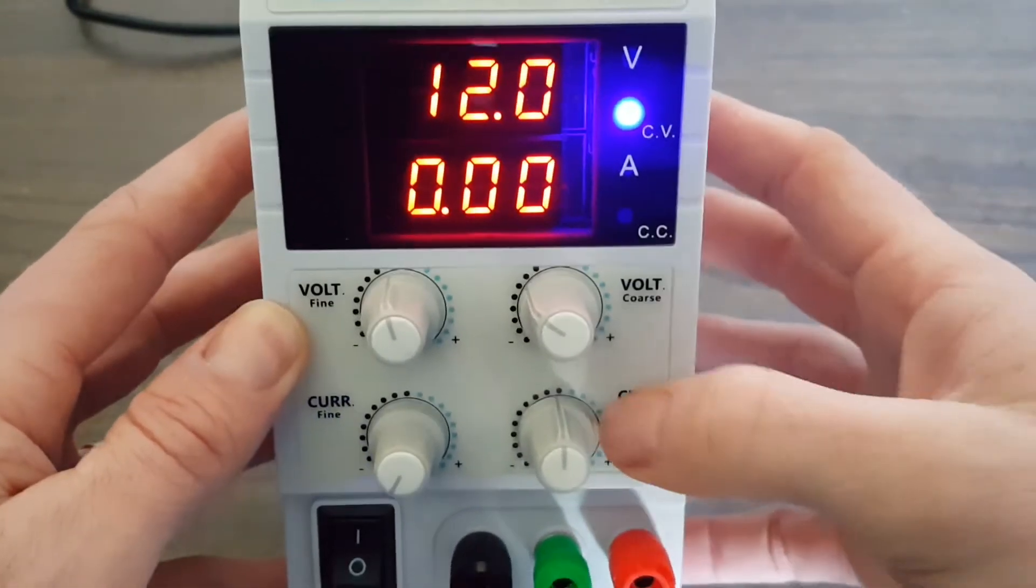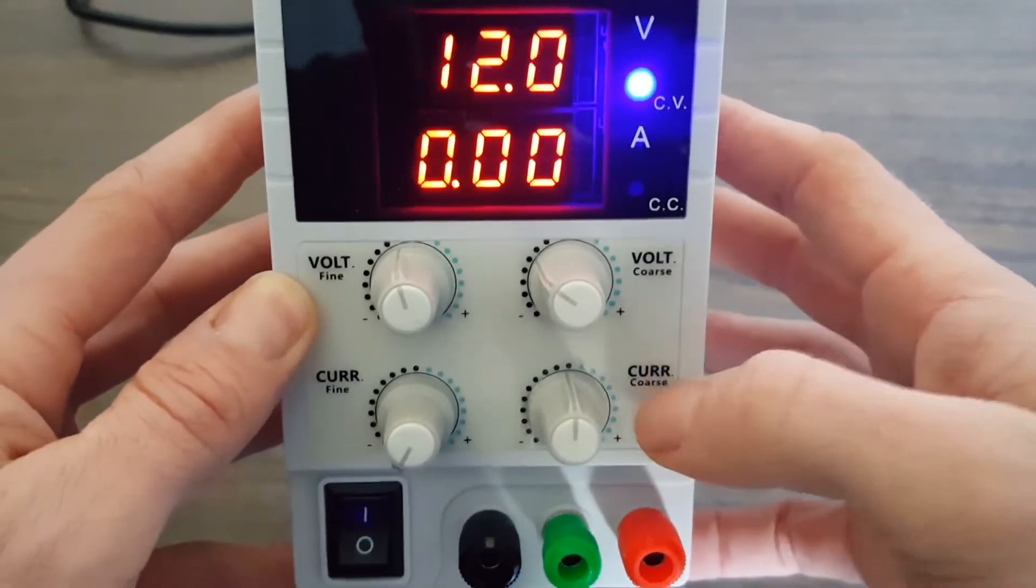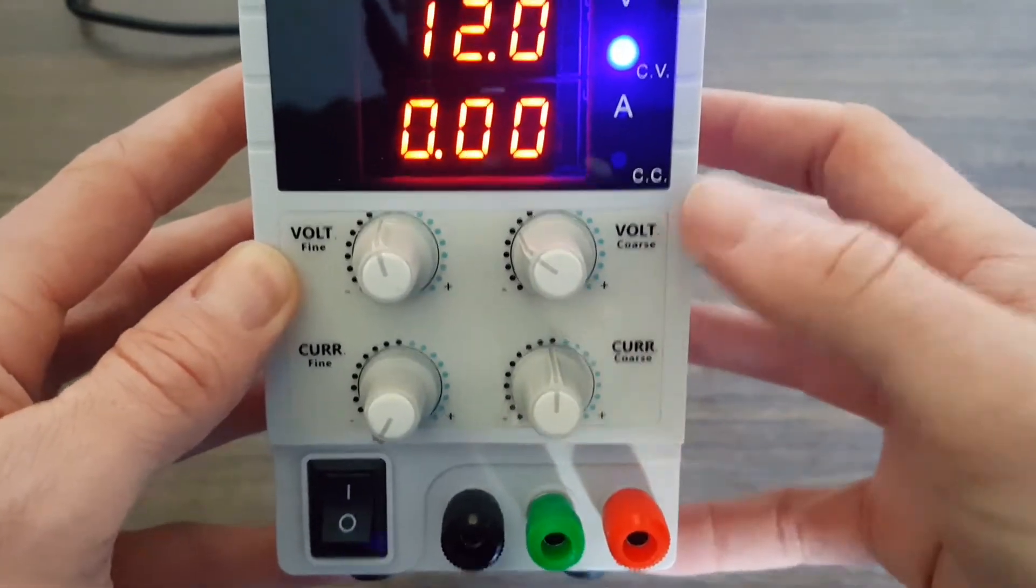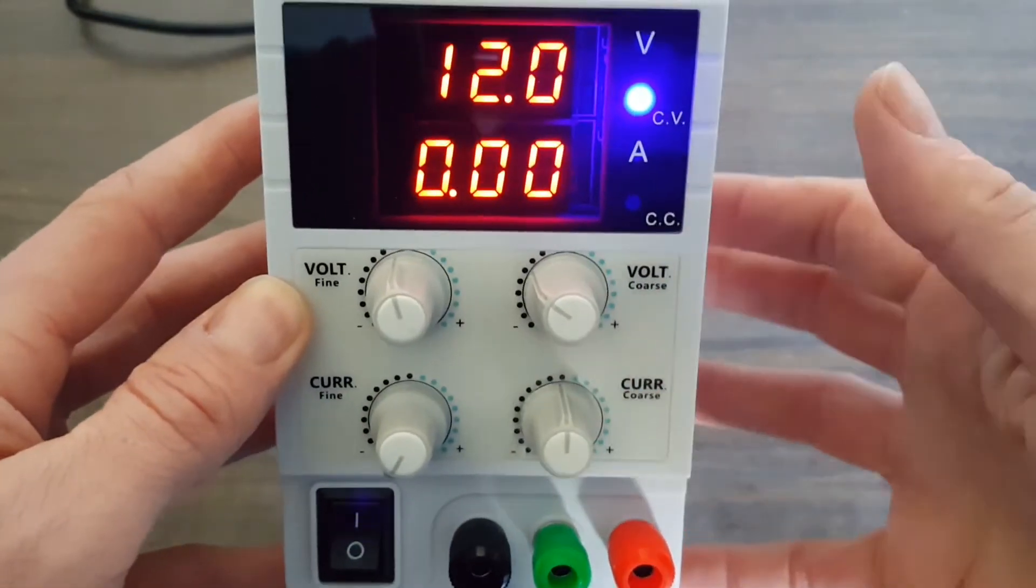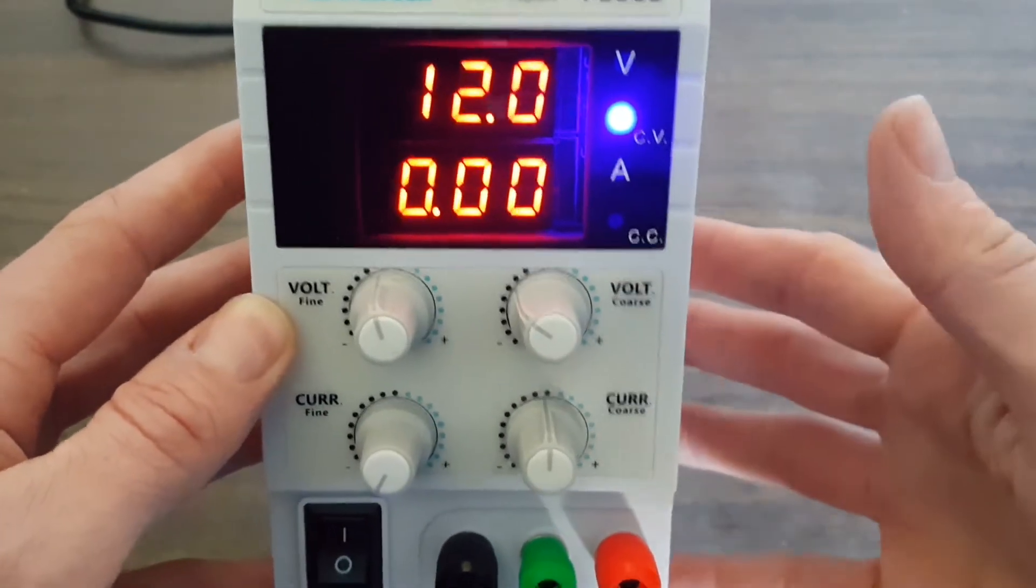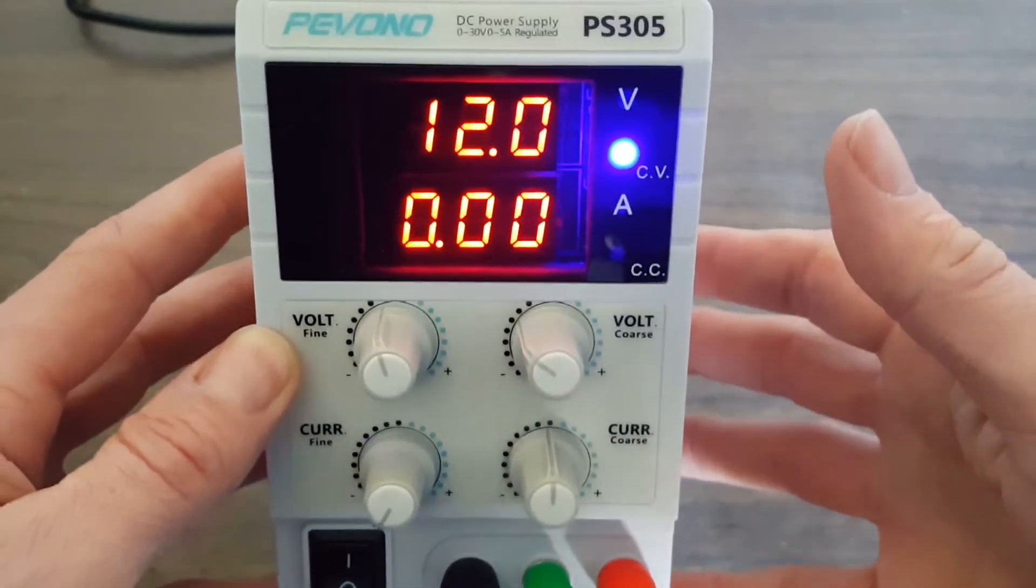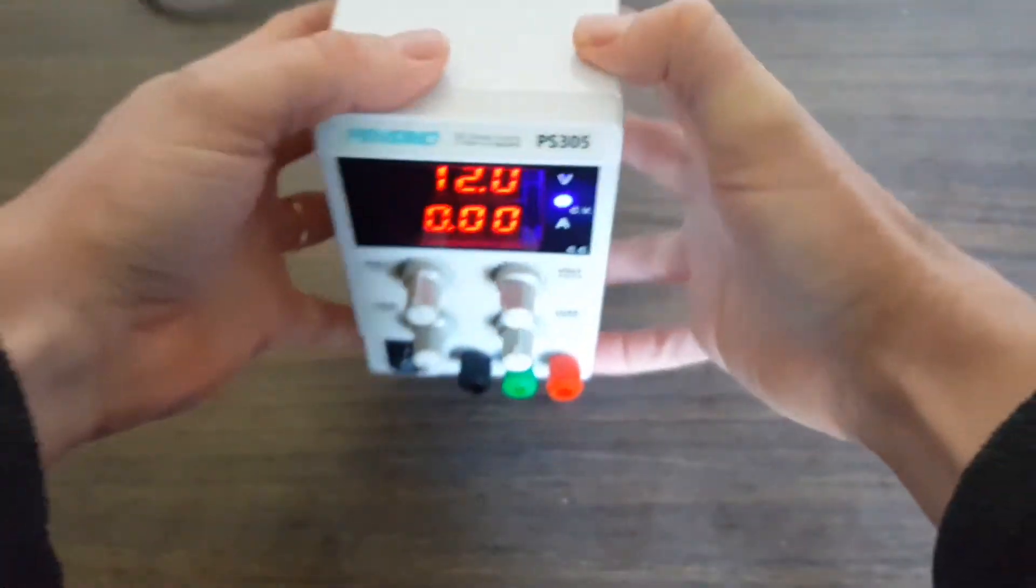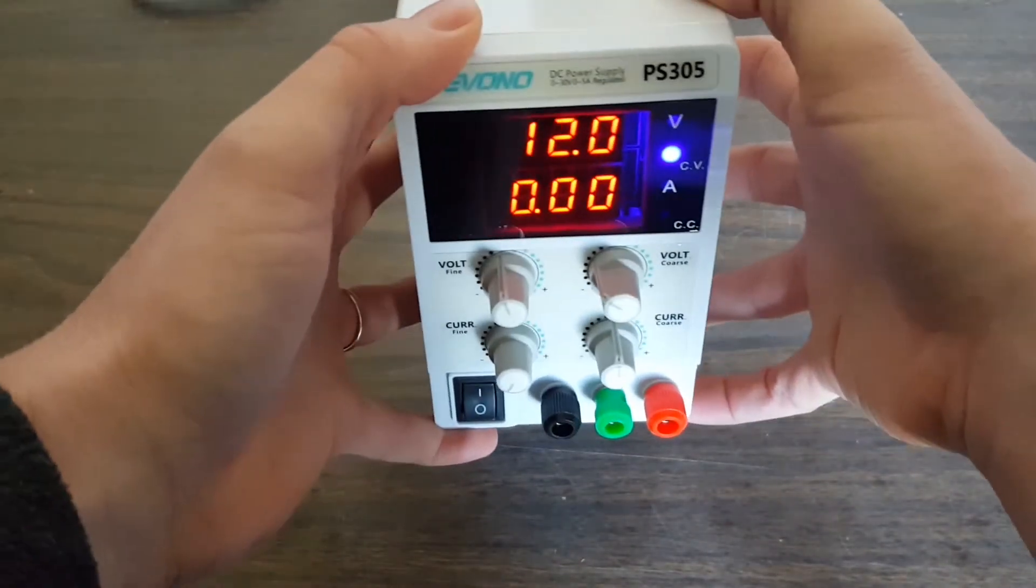As we put this thing under load, if the current load exceeds the setting, it's going to limit the voltage to only allow the set current to flow through the unit and through the device connected to it. So let's hook up the multimeter and we'll check out our accuracy here.